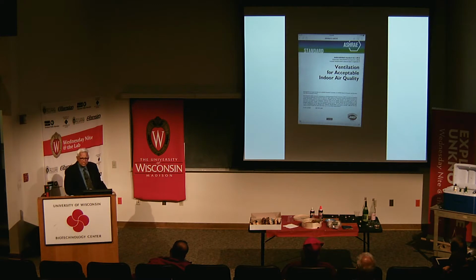Again, ventilation standards are available from ASHRAE. They have the standards for ventilation. I said about CO2, they have the standards on how to calculate ventilation rates to account for CO2 and also any volatile organic compounds, VOC, that may occur because of furnishings and all that.